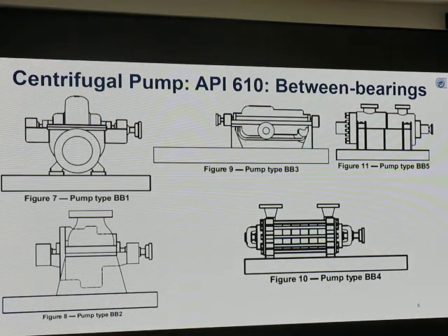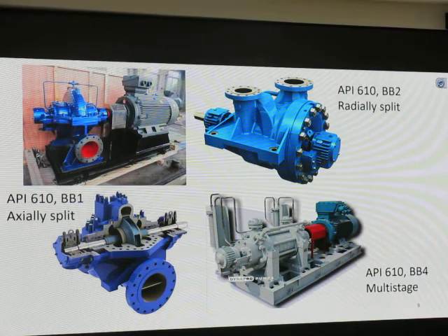One thing you want to know is how it looks. When it is a centrifugal pump, internally it has blades. Externally, we have to put a bolt or several bolts to connect it together. Sometimes these bolts are arranged in a circle shape, radially. So this we call radially split. Sometimes the bolts are not in a circle. Sometimes the bolts come from the top, and the shape is irregular. When we remove the bolts, we take the top part out. This time we call it axially split. Memorize this.